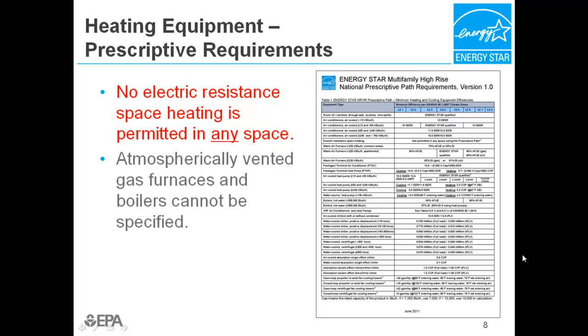The next few slides will review examples of the prescriptive requirements related to heating equipment. When following the prescriptive path, no electric resistance space heating is permitted in any space in any climate zone. If the design cannot avoid electric resistance heating, then the performance path would need to be followed instead. Atmospherically vented furnaces and boilers cannot be specified in any climate zone. This is the same prerequisite as in the performance path.